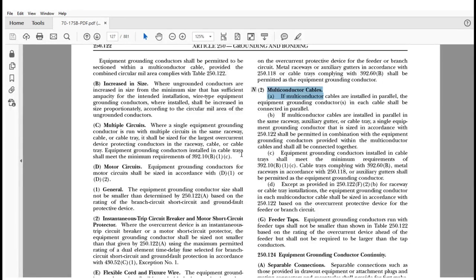Let's see. Again, the rationale was running a separate equipment grounding conductor in a raceway, auxiliary gutter, or cable tray will provide an adequate fault current path while allowing the use of a commercially available cable wiring method. Like I said, we make MC cable with the equipment grounding conductor based on the requirements of UL 1569 and based on the perceived overcurrent protective device to be utilized with the conductors that are in that cable. Not for when you run it in parallel, because all of those factors change. Can you order them specially for that? Yep. It is not an off-the-shelf thing, I can promise you.